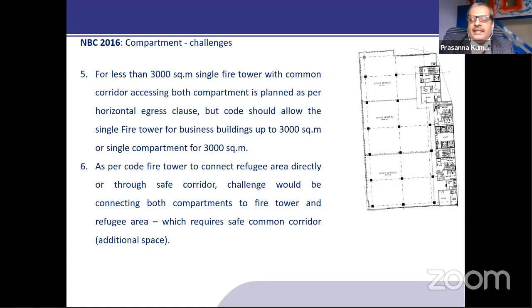But the concern here is when there are smaller floor plates, we need common corridors to evacuate both compartments to the refuge areas. These corridors have to be made safe. Because the floor plate is smaller, a lot of service room doors open into these corridors. I'm highlighting this based on my exposure with many projects, discussing with architects and developers how to treat electrical rooms and shafts opening into the corridors, to make it a safe corridor.